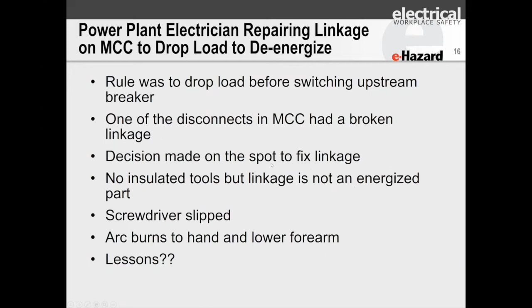Now, what are the lessons there? The lessons are never skip the safety rules. When you're supposed to be using insulated tools, use insulated tools. Once you're inside that restricted approach boundary, or really the limited approach boundary for insulated tools, all the tools should be insulated, rubber gloves should be worn, because you've now crossed the restricted approach boundary. So if there's anything in there you could inadvertently touch, according to the standard, you have to be protected from that. So this would have been a simple fix, but breaking that rule makes a big difference.